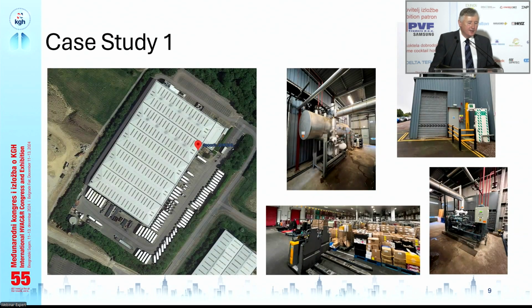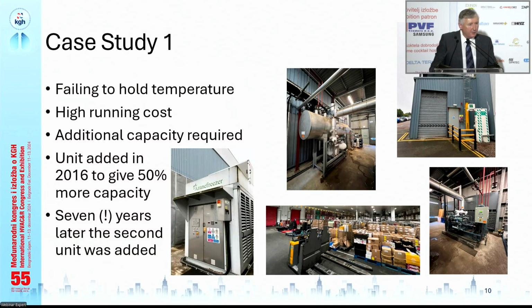So here's a first case study. This is a warehouse in England which is used for supplying a restaurant chain all over the country, and it had a pumped ammonia system, but it was struggling to maintain the store temperature. So the customer thought, I need to add a bit of refrigeration capacity. You can see the plant room down here, a surge drum, a compressor pack, a duo pack with 2 screw compressors, evaporative condenser on the roof of the plant. This ought to be quite a neat, efficient system, and it's serving both chill areas and low temperature areas within the store. The plant was failing to hold temperature.